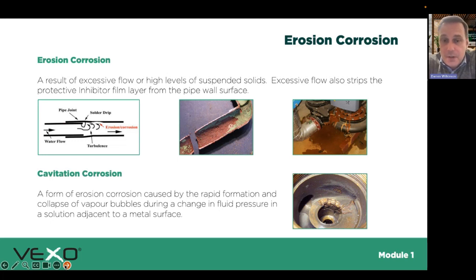Particularly as well, erosion corrosion, if you've got deposits, once again, it's like shot blasting. You're going to have pump seals failing. So it's normally the first giveaway. If you're getting pump seal leaks, chances are you've got a water quality issue rather than a pump seal issue. Generally, pump manufacturers don't make bad pump seals.